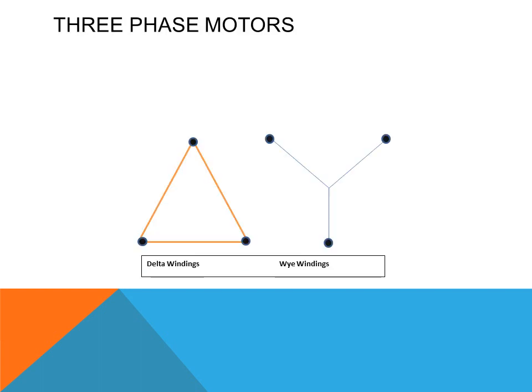This is a basic diagram of two different types of three-phase motors. The second one is Y — if you notice, it is connected at the center from the three separate windings. The delta is connected on the outside, connecting its three windings. Three-phase motors are pretty versatile and they can be wired for higher voltage like 480 volts or wired for low voltage like 230 or 208 volts.